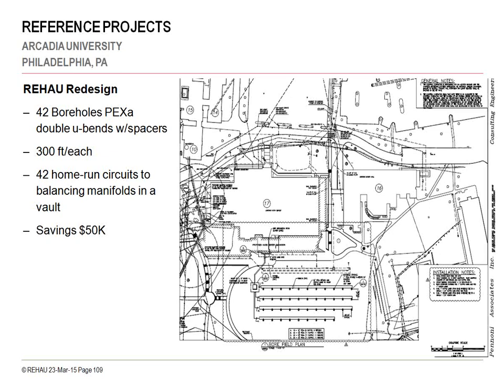The other thing here is that with this redesign, with the PEXA materials for the 42 boreholes, there was a $50,000 savings compared to the low bid of the HDPE design. And that $50,000 is after having the cost of the vault and the balancing manifolds that I mentioned in this redesign.